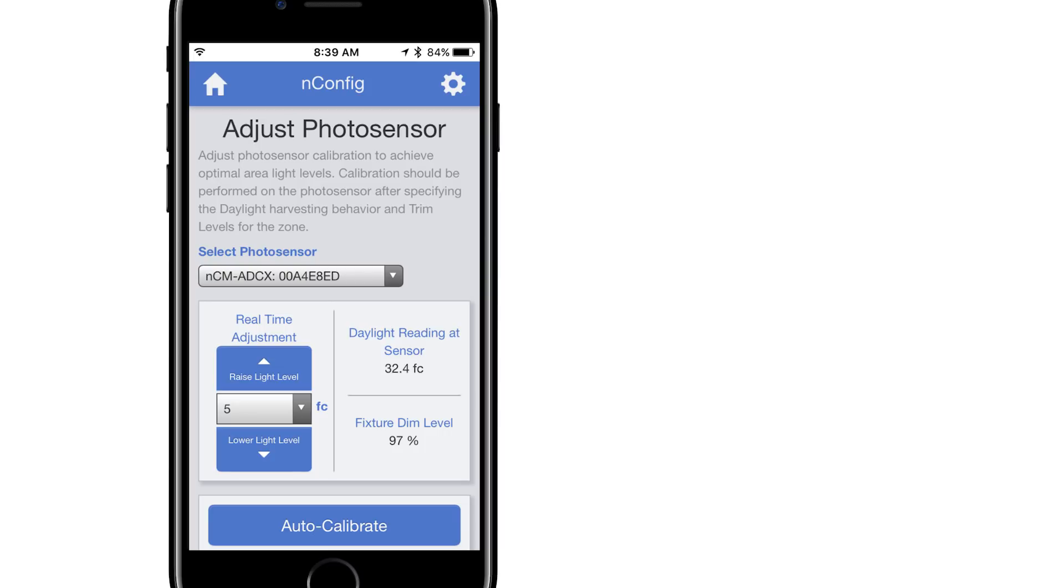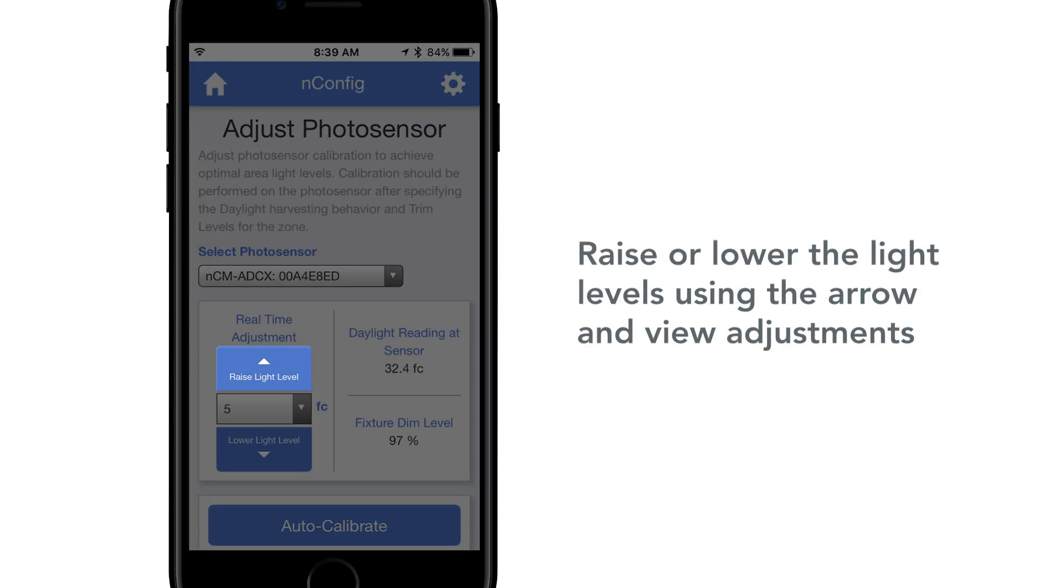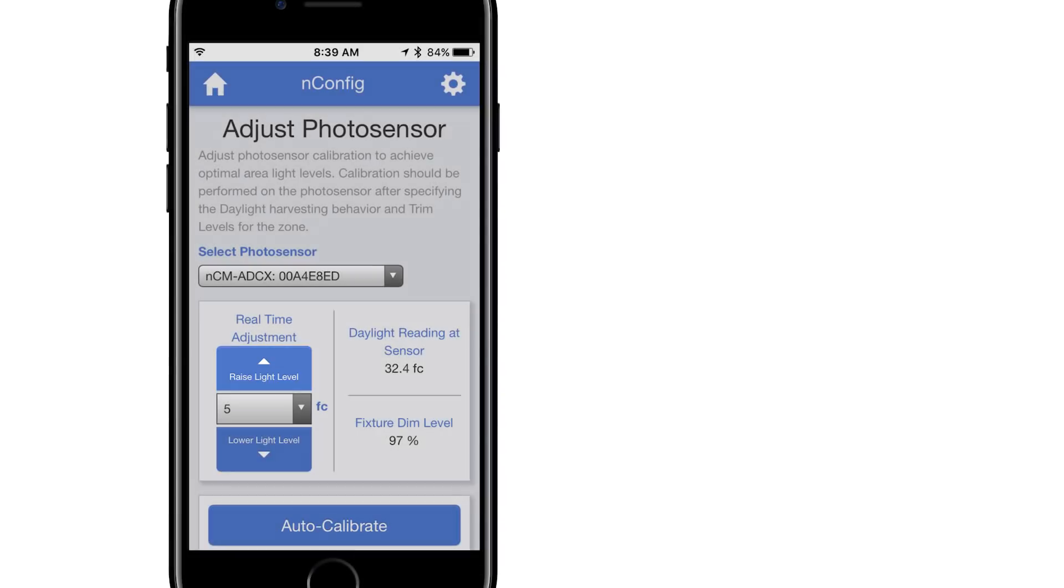If you find the fixture dim level is at 1% and you desire more light in the space, use the Raise Light Level arrow and make adjustments until you see this level begin to climb. Please wait a few seconds between each press of the arrow to allow the sensor dimming level to adjust, since these are live running changes.